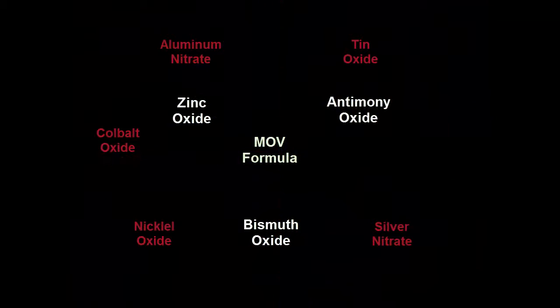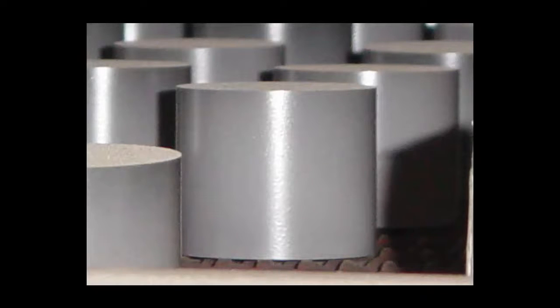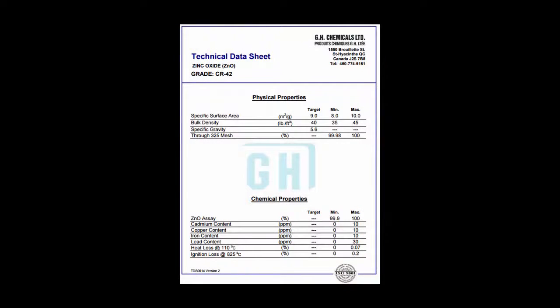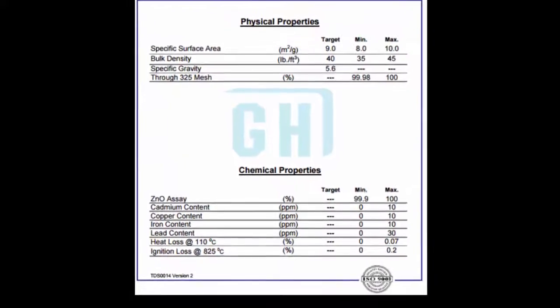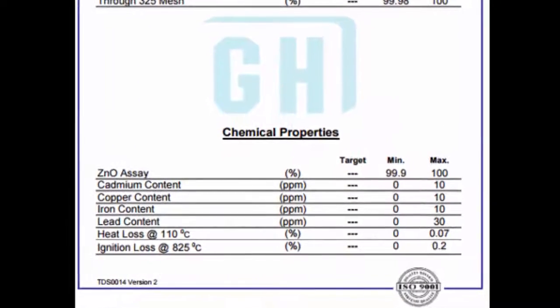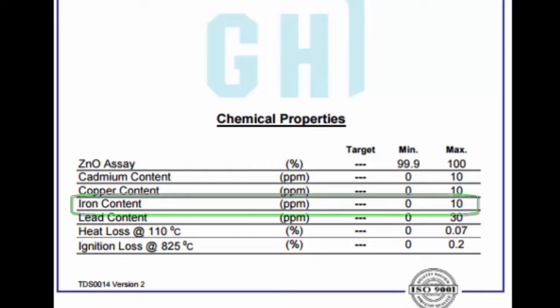The source of these materials and control of the quality of these materials is paramount to the end quality of a disc. Keeping impurities at a minimum is a major task and is critical to disc quality. Each of the raw materials has a specification which states the limits of impurities. On this typical zinc oxide specification sheet, it shows that the maximum iron content is less than 10 ppm, or parts per million. Too much of this impurity can cause the clamping voltage of a disc to be higher than desired, which in turn will result in less protection.